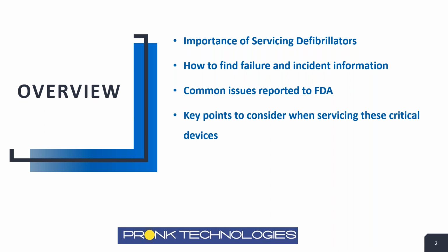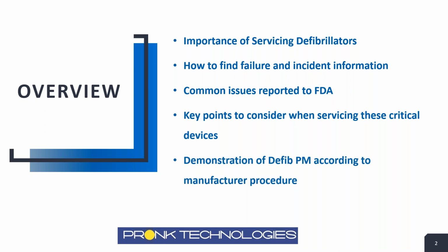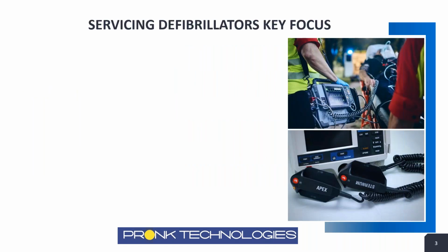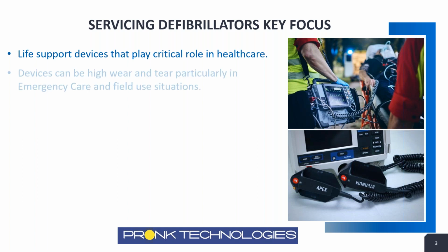Key points to consider beyond the FDA when we're servicing defibrillators that I think will be important to cover. And we're also going to have an actual demonstration of performing a PM on a defibrillator, following the manufacturer's procedure, highlighting just some of the key things to be aware of and how to perform these key tests when we're doing the service on defibrillators. So let's get started. Servicing defibrillators, of course, is a very key focus in healthcare. These are life support devices that play a critical role in healthcare, so it's important that we service these to the best of our ability.